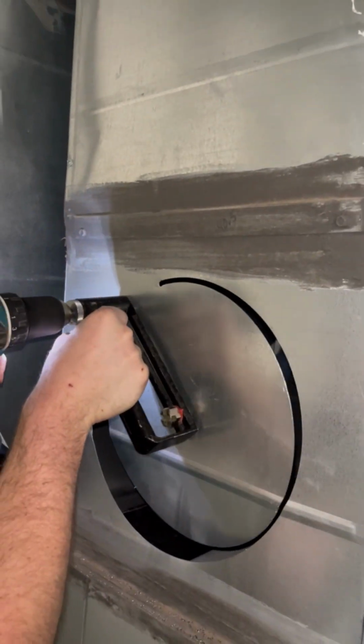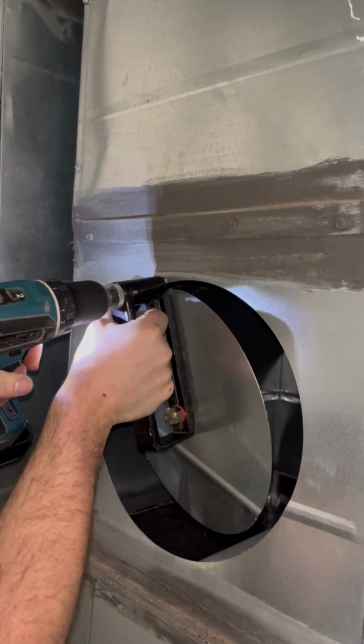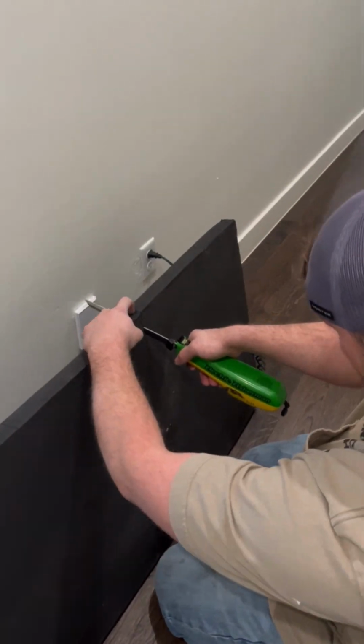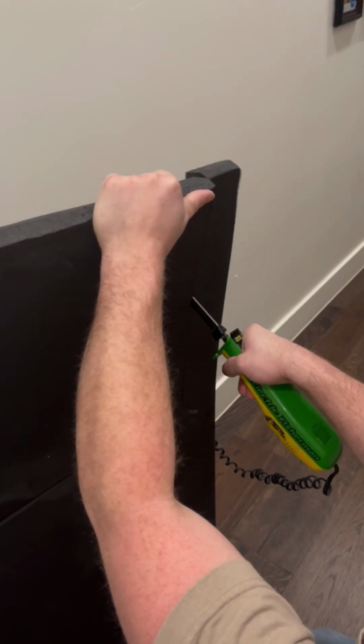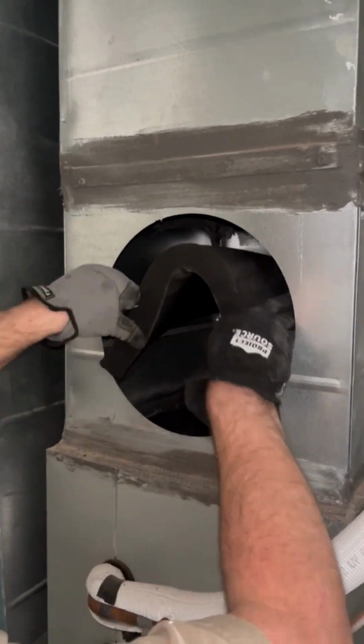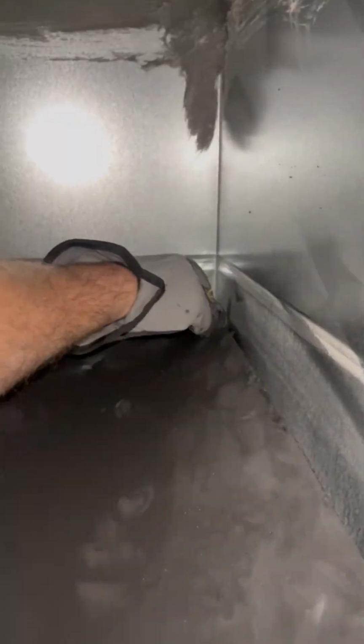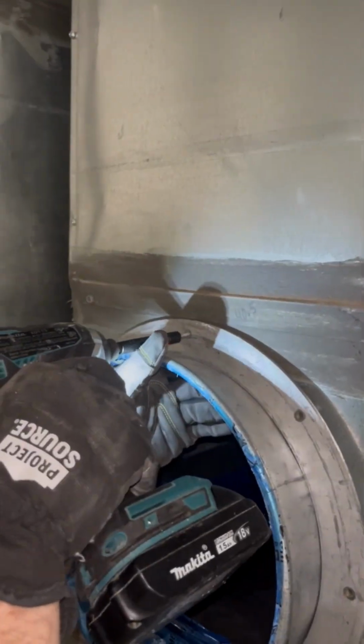Once we finish cutting the circular opening, we'll get measurements to see what size plug we need to keep all the glue out of the furnace. After a custom-sized plug is cut, we insert that inside and then we'll push all the corners down to make it airtight. Not only do we use the plug, but we will actually use some specific sealing tape to make sure that no air can get down into the coils or anywhere inside the furnace.